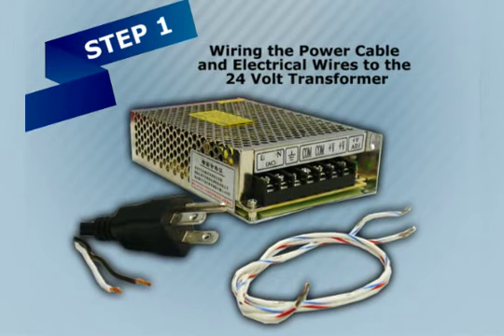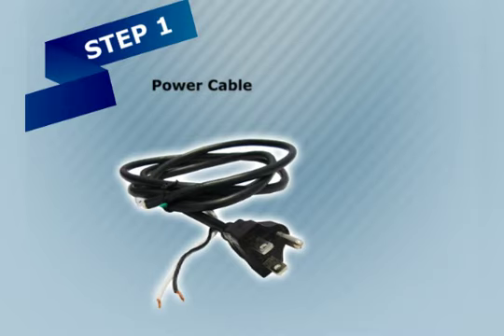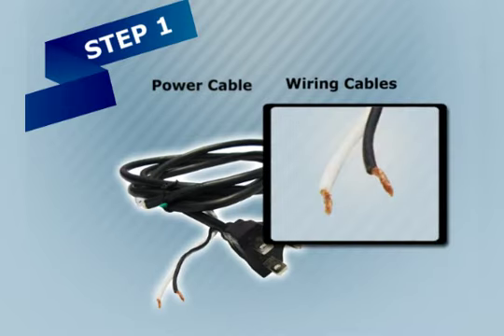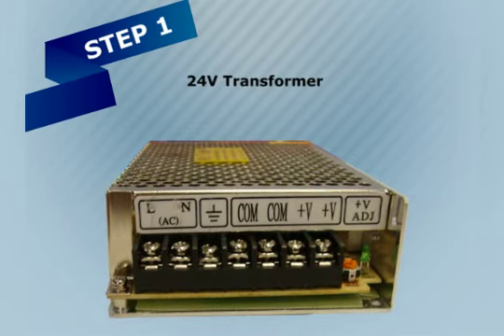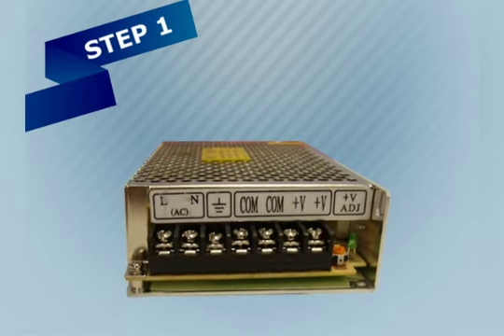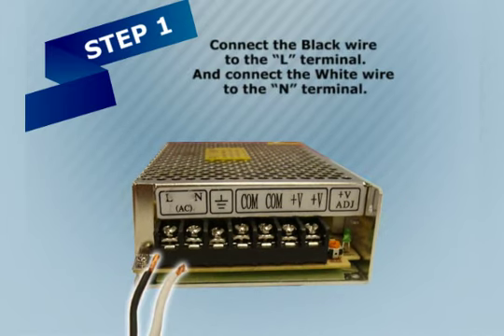Step 1. Wiring the power cable and electrical wires to the 24-volt transformer. Take the power cable. Locate the wires you will be using for positive and negative connection. On the 24-volt transformer, locate the positive and negative connection terminals. In this transformer we will be connecting to the L and N terminals. For this installation we will connect the black wire to the L terminal, and connect the white wire to the N terminal.